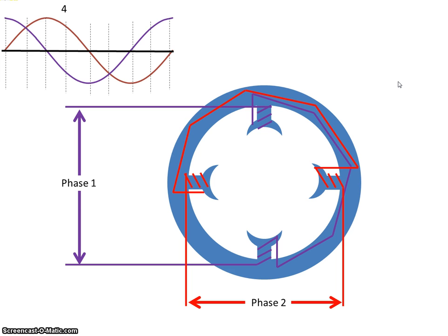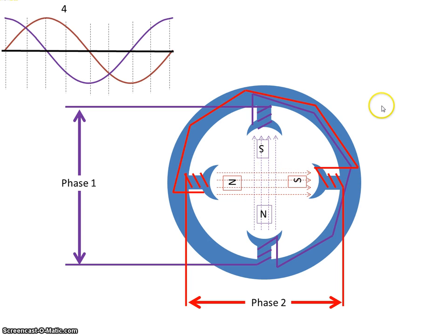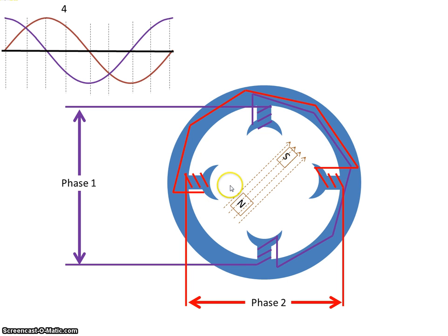At time four, phase two is still positive but phase one has now gone negative, therefore the current is flowing in the opposite direction on that winding, so the north pole is now here for this phase. And on phase two the north is still there, so the flux lines are in this direction. Again the flux lines can't cross, so we take up an intermediary position which is somewhere there. So our north pole has moved from there to here to here and now in that direction.